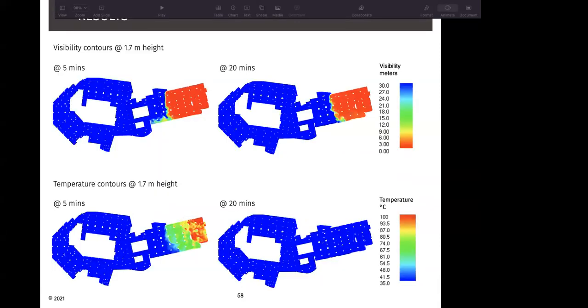concentrated in that area. Now, looking at the visibility and temperature contours, we see that the visibility is completely zero for that particular part of the car park at 5 minutes as well as 20 minutes. The temperature is back to normal. We've taken an ambient temperature of 35 degrees. By 20 minutes, because the fire has stopped and the fuel has been cut off, we assume a 20-minute fire, the temperature has dropped, but the smoke remains in that area as cold smoke. That would reduce visibility, and that would cause problems for people evacuating or firefighters trying to access the fire location.